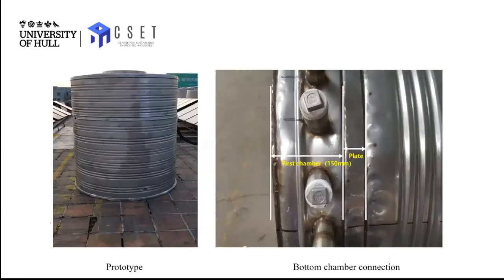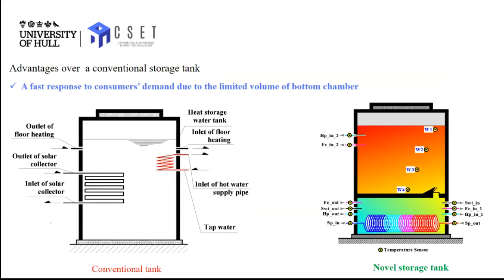So this is a storage tank. In the low part, we have quite a number of connectors that allow the heat exchanger to connect to the solar loop and the heating loop. Compared to traditional heat storage, which is slow to respond to heat demand because you have quite a large volume, maybe 1 cubic meter or 2 cubic meters, heating can be made available only after we heat up this amount of water, which takes at least 3 or 4 hours. In that case, we need the heat pump to switch on during morning time, with significant electric consumption and less utilization of solar energy. Our technology can overcome this difficulty and challenge and minimize the use of the heat pump.